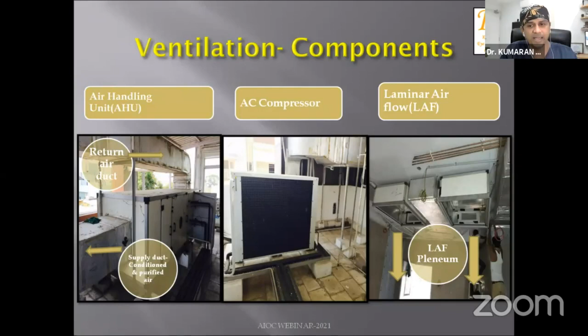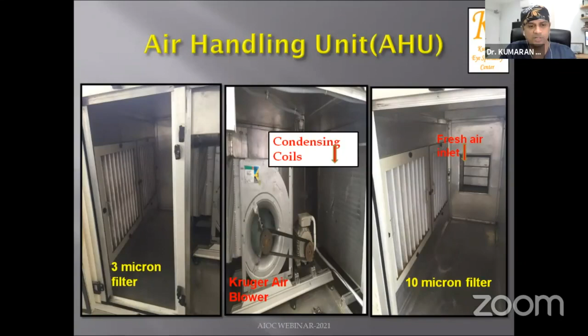The HVAC system consists of 3 parts: an air handling unit, a compressor, and a laminar airflow through which the air is cleaned, filtered by a 10 micron and a 3 micron filter, and blown through an air blower into the theater from the ceiling, so that you get a uniform laminar flow of air across the tables, which carries all the pathogens floating around the theater into the return ducts, which are usually placed around 1.5 meters above the floor level.